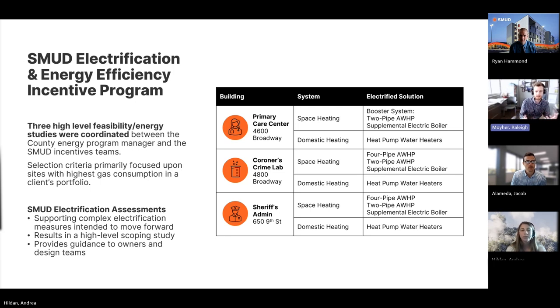You can have this older 180 degree, sometimes even 190 degree system, and you're trying to bring in this heat pump water heating system that might be targeted at delivering 140 degree temperatures. You could bring in just this supplemental downstream in-series unit to boost that water temperature up. I saw that as a potential huge win, because it keeps us from upsizing all of our infrastructure, like the hot water piping. Specifically, I remember looking at the Coroner Crime Lab and seeing all the spidering out of our hot water piping to the hot water coils for air handlers that are custom built into space, tiny little closets. We had VAV boxes with coils that would have needed upsizing. So it was a nice way, from a design perspective, to zoom out a bit and sort of brute force the old system into being electrified.